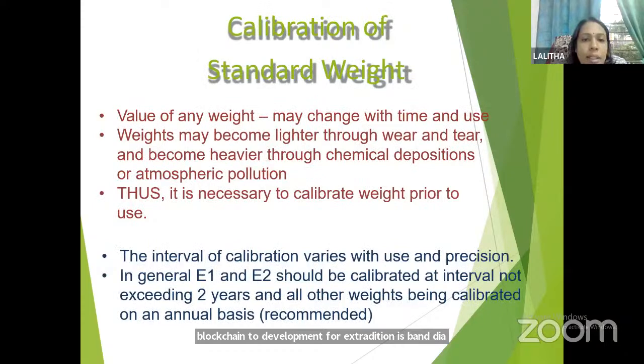Standard weight calibration. The value of any weight may change with time and use. Weights may become lighter through wear and tear and become heavier through chemical deposition or atmospheric pollution. Thus, it is necessary to calibrate the weight prior to use. The interval of calibration varies with use and precision. In general, E1 and E2 should be calibrated at intervals not exceeding 2 years, and all other weights should be calibrated on an annual basis, as recommended by the company.